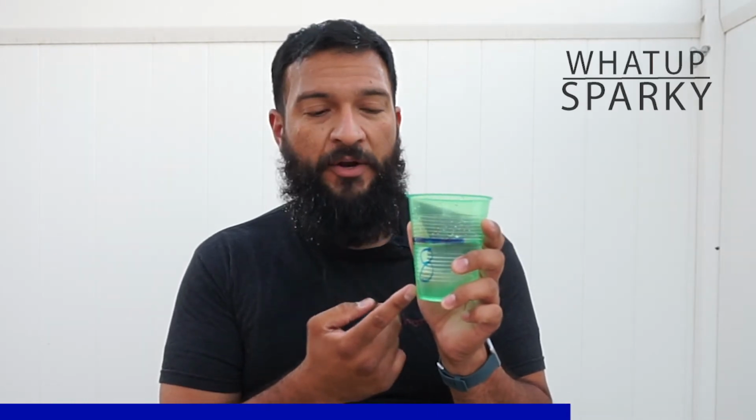Now let's talk about the other panel. It's upstream, the same 8 ounces of water, but there's more flow there. Let's take a look at this situation. I have my hands in this panel again and I'm working on it, and then all of a sudden it falls apart. What happened here? Well, it was a lot more flow, but the breaker shut off a lot quicker, so it was over a shorter period of time. But I still ended up with the same 8 ounces of water, or 8 calories of incident energy, hitting me.